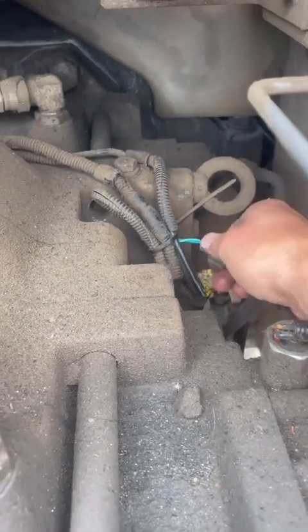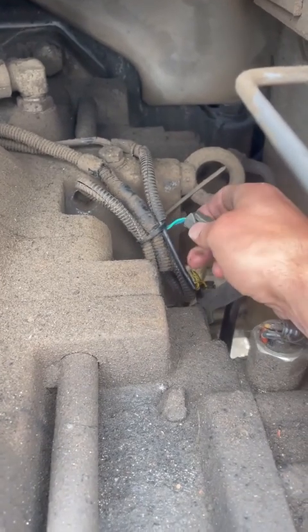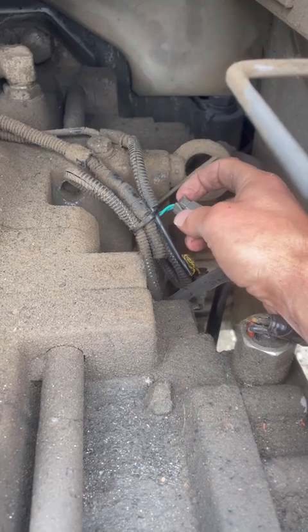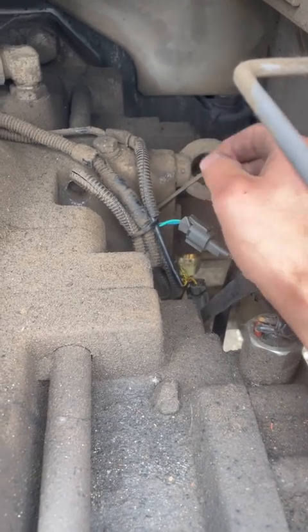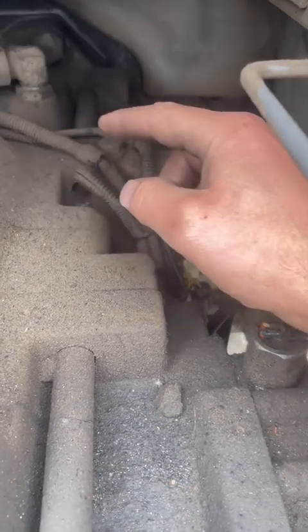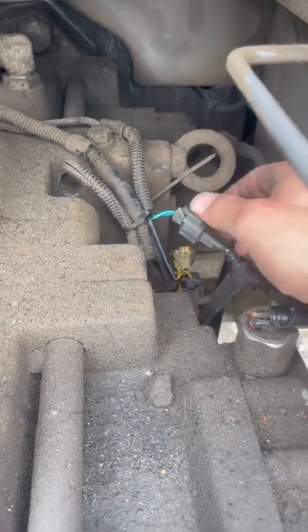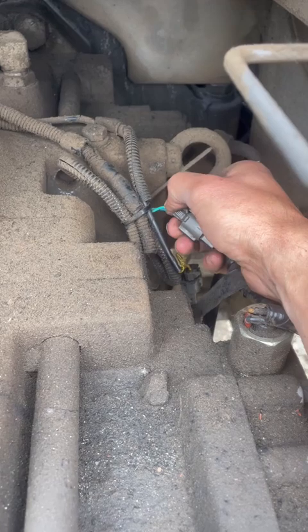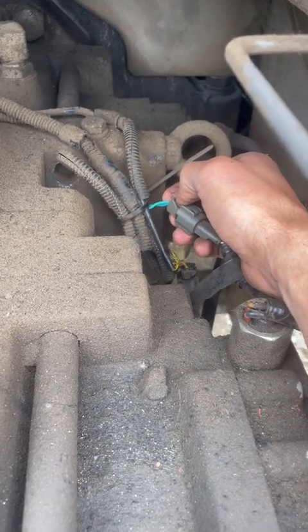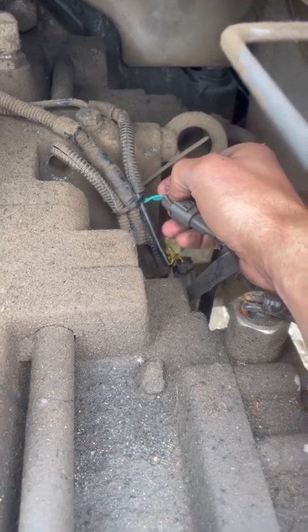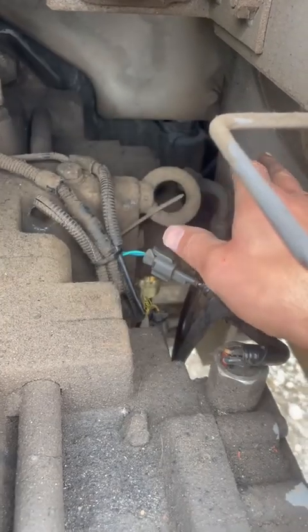So the service manual might tell you to go to this connector and check from pin A to pin B and you should have X amount of volts. Or to check from these back to the controller, you should have so many ohms of resistance. But one strand of this wire will carry system voltage and it will give you a good ohm reading. So I came back here with a meter and all that checked out.